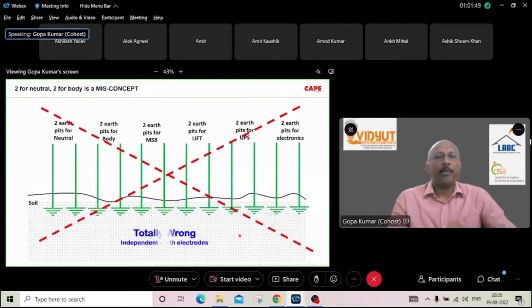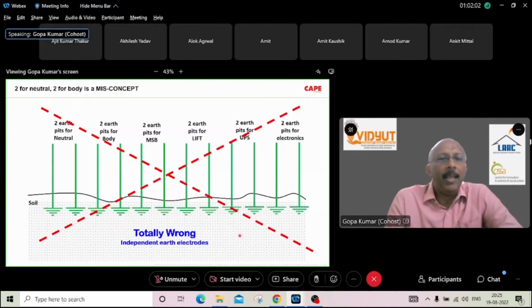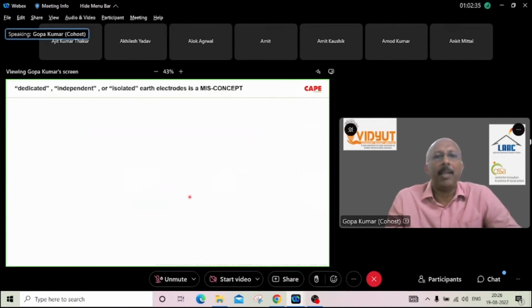These mistakes we start making. The whole story of electrical safety, or the whole method of these accidents, the primary reason for these accidents is this kind of illegal way of earthing. It is never written or documented in any of the Indian or international standards, but people start following a system which is a big mistake. For a joke, I call this 2 for neutral, 2 for body. That means whenever we talk about earthing, people say, yes, I have a transformer, I have connected the neutral to two earth pits, body connected to two more earth pits. Please understand that it is completely wrong, and this is the main reason for accidents.